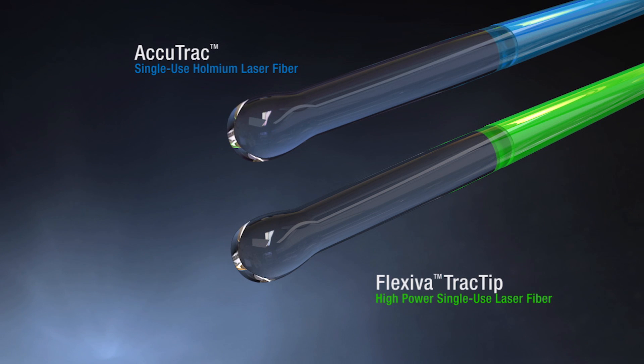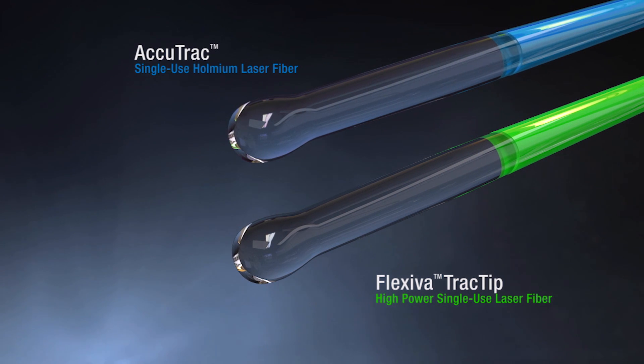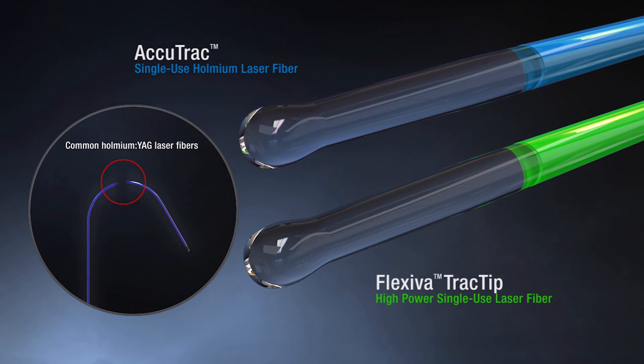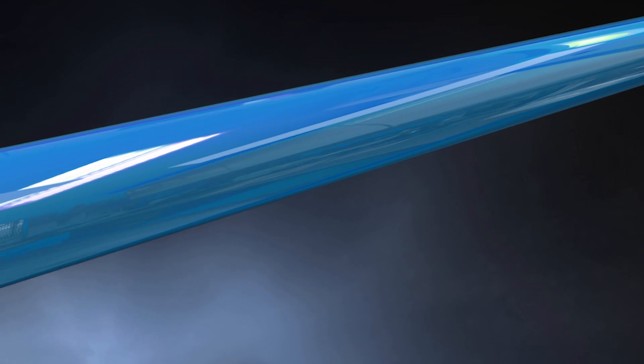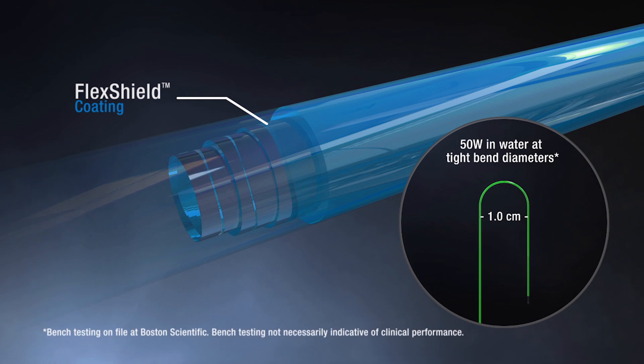The AccuTrac and Flexiva Track Tip Laser Fibers have other differentiating design features for performance in the most challenging ureteroscopic cases. A common cause of scope damage is fiber breakage due to leakage of laser energy. Therefore, these fibers are equipped with a proprietary FlexShield coating designed to withstand high power ratings up to 50 watts at tight bend diameters as small as 1.0 cm.